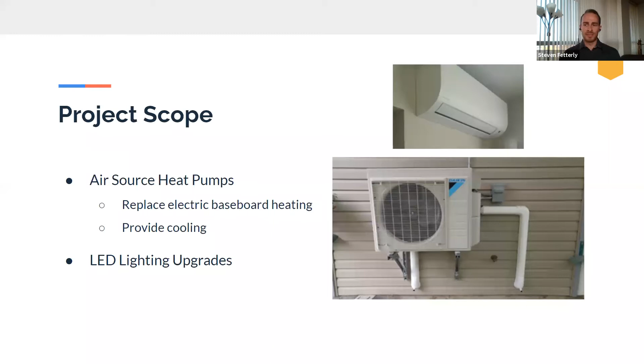For a bit more detail on the mini split heat pump systems, the idea was to install a mini split system at each individual suite, if the tenant suites were individually metered, or a multi-zone system at that long-term care facility where the society paid for all of the utility bills. On average, a lot of the suites are about 600 to 700 square feet, which resulted in several small heat pumps to do the heating and cooling of the space, about 3/4 to 2 tons of capacity. The good news here was that those small units typically only require 15 to 25 amp breakers, which were very common in these buildings. And that enabled us to retain backup heating by the electric baseboards for any peak heating during winter design conditions, as well as provide some redundancy in different rooms.